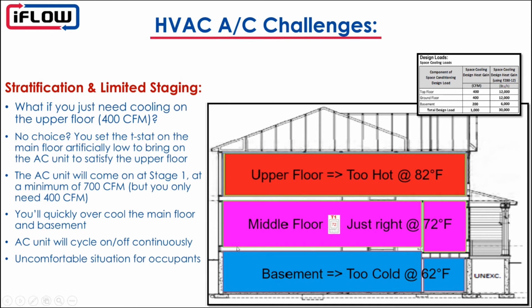So let's say this is the situation. We're in the middle of summer, where our cooling load is worst. The thermostat, it's not a zone system, so the thermostat's typically on the main floor in the middle of the home, and let's say it's just right at 72 degrees, so it's perfect. But unfortunately, as we all know, the upper floors, with heat rising, often get too warm, and then the basement is often too cold in the summer.